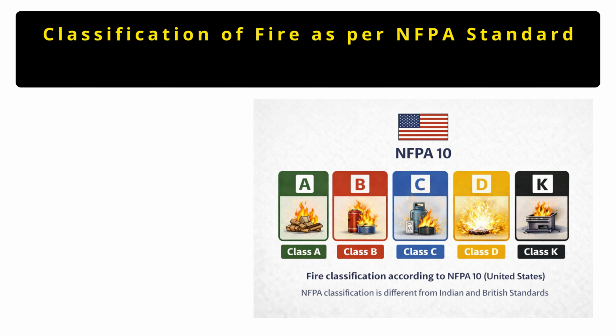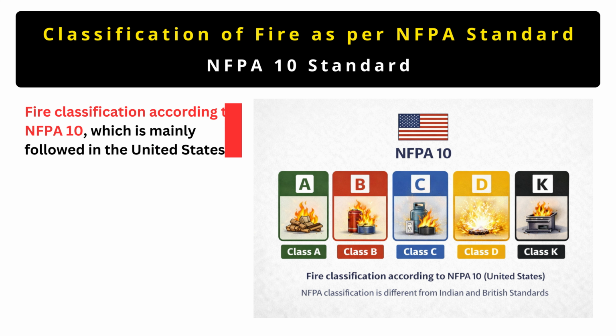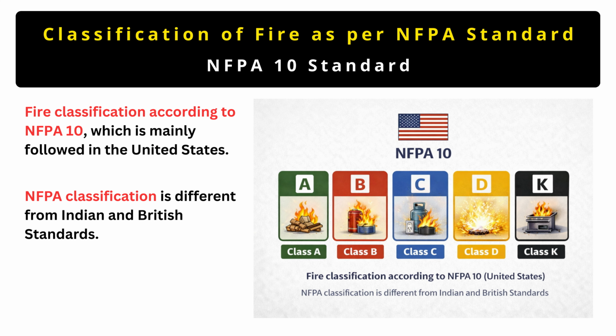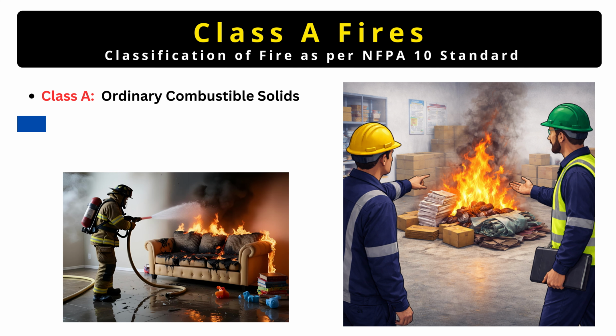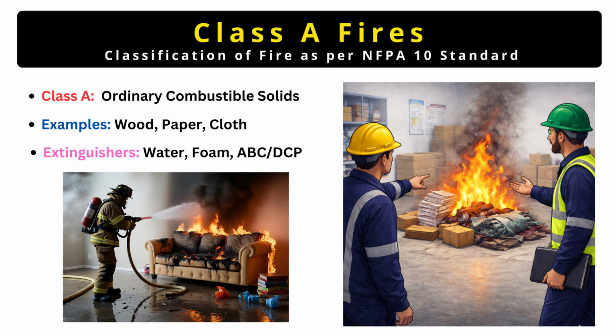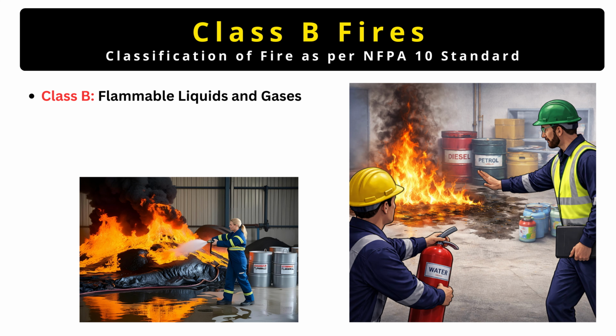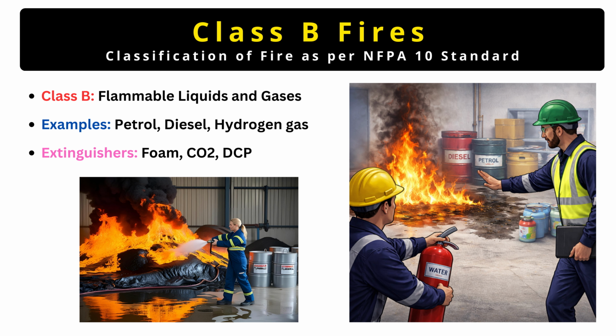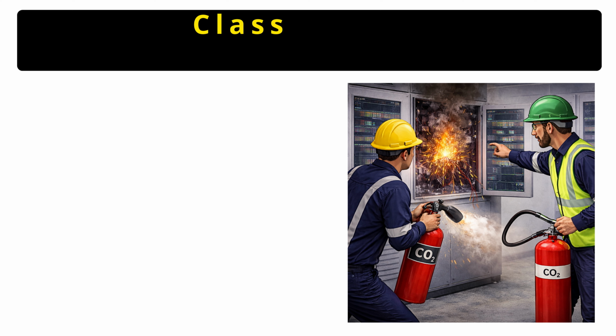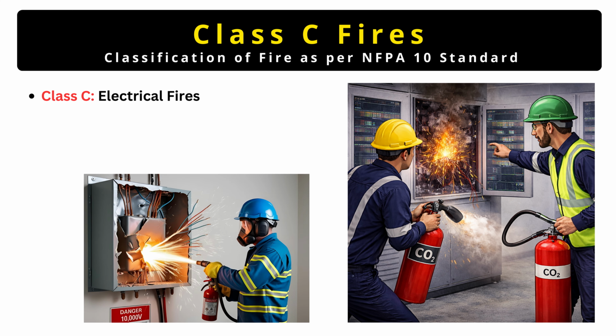Now let us understand fire classification according to NFPA 10, the National Fire Protection Association 10, which is mainly followed in the United States. NFPA classification is different from Indian and British standards. Class A fire involves ordinary combustible solids. Examples include wood, paper, cloth. In NFPA, flammable liquids and flammable gases are combined into one class, which is Class B. Examples include petrol, diesel, hydrogen gas. This is a major difference compared to Indian and British standards. In NFPA, Class C fire refers to electrical fires.